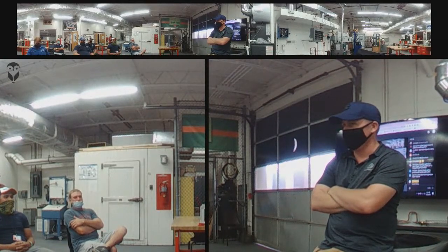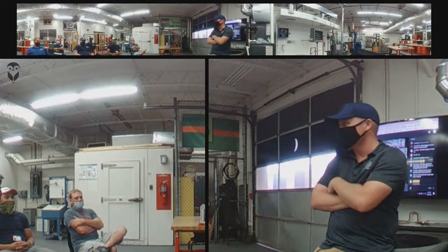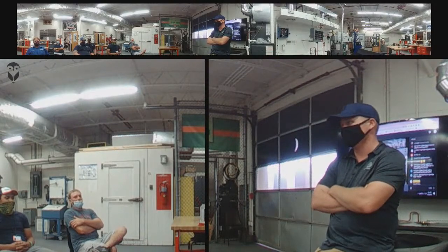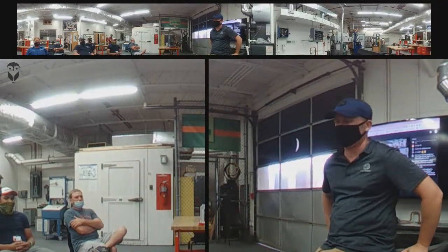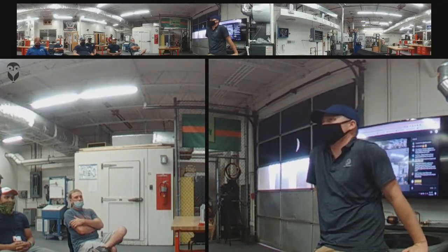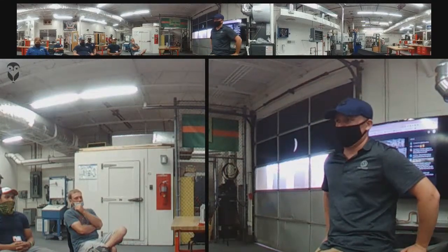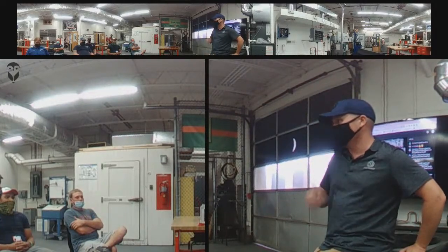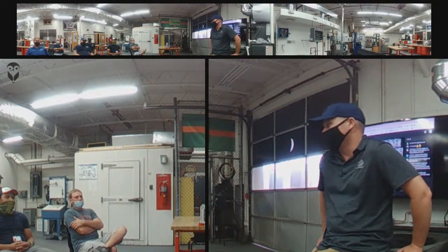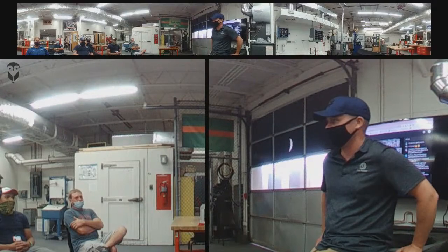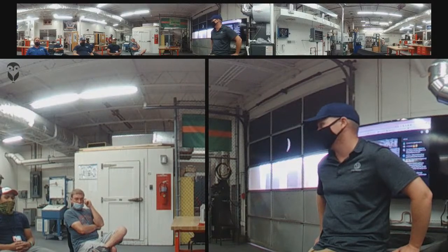Attic units are tough. And like we talked about, anytime you're installing a unit horizontally, pay extra attention to condensate. Pay extra attention to the installation manual. Make sure that everything is configured the way it's supposed to be. And in attics, this is something that gets missed quite often: the dew point in attics can be extremely high. So you're going to have more unit sweating problems in attics than pretty much anywhere. And sometimes there's not really great solutions other than trying to keep your airflow up so that your cabinet doesn't get too cold. But those are all things to look at. But yeah, long day, sounds like.